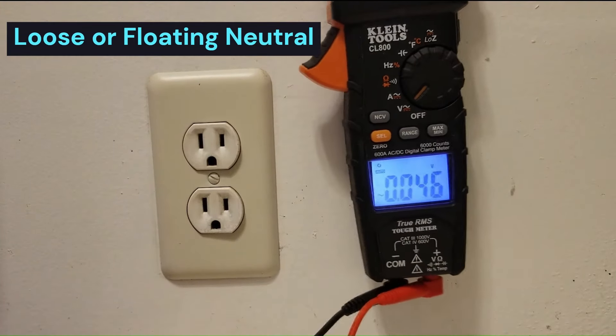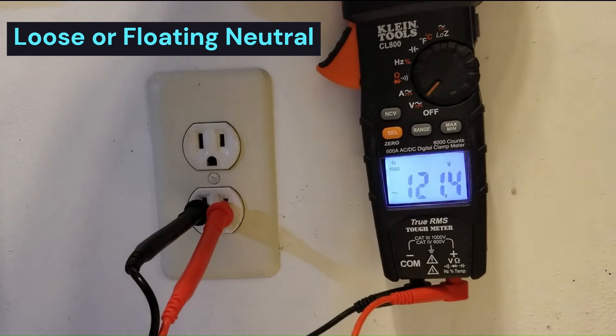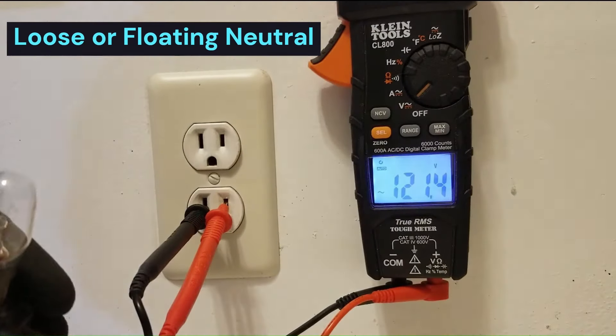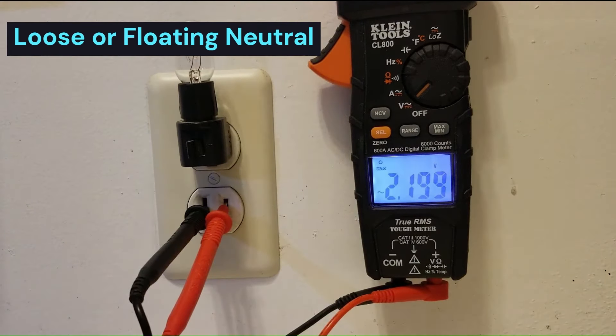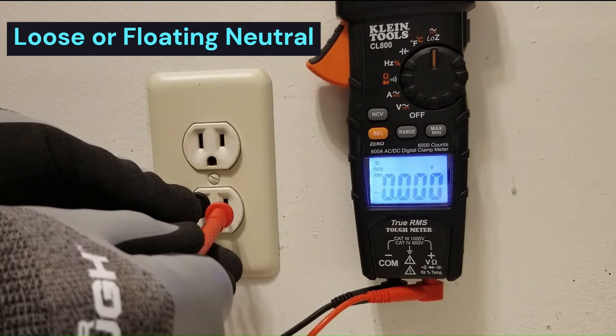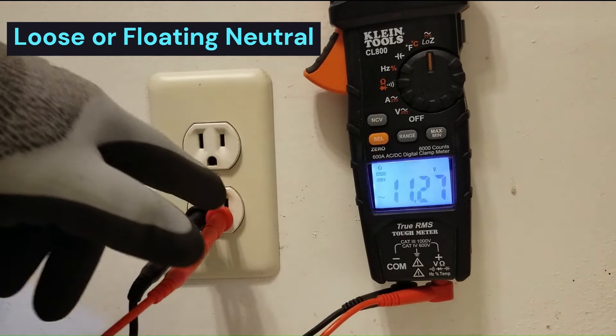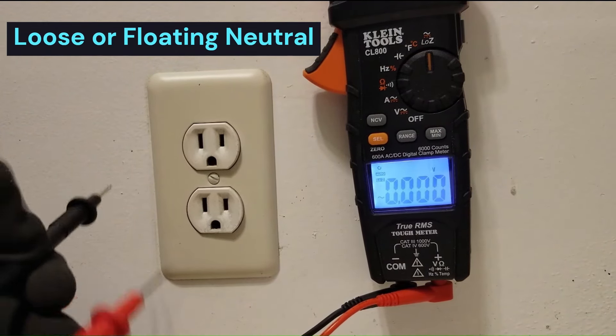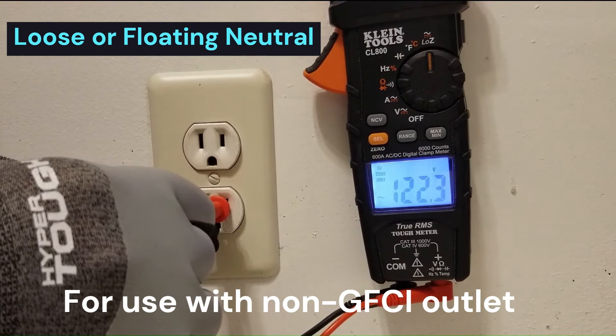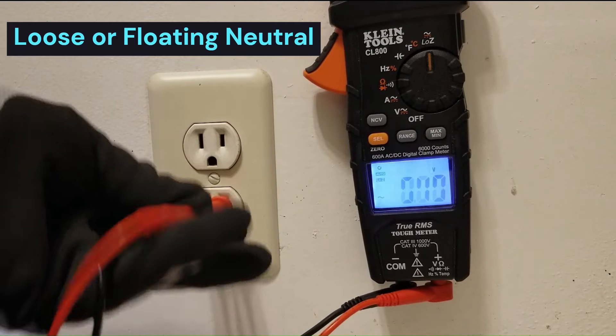If I test this outlet, it's going to tell me that we have a good outlet - it's reading 121 volts. But I know it's not a good outlet because if I plug this night light with a four-watt bulb into it, look what happens: it kills the outlet, knocks it down to about two volts. So I'm going to switch to low-Z mode. Now we're only reading 11.2 volts. What is this caused by - a loose neutral or a loose hot? You could measure from ground to hot, and in this case we get 122 volts. So that tells us that the hot lead is okay, and by process of elimination, that tells us there must be an issue with the neutral line.